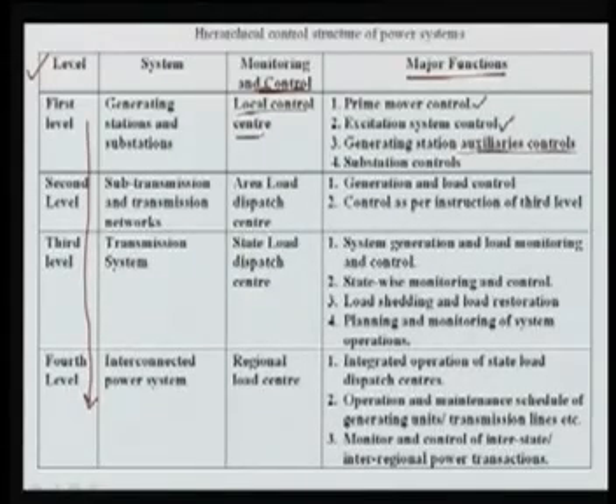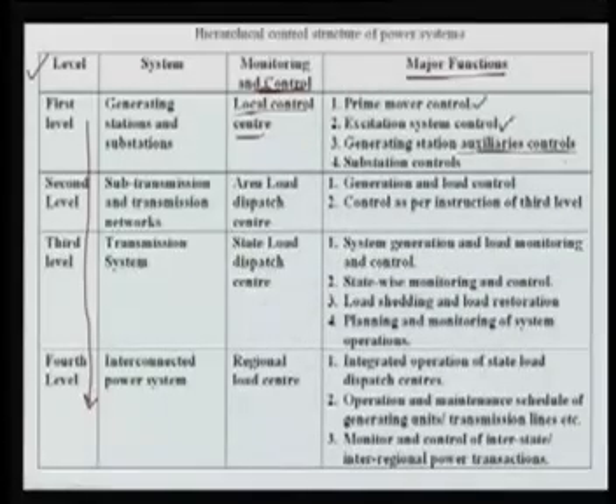You know, in any generating station we have a lot of auxiliaries. We have to have several auxiliaries for generating a single megawatt of power. For example, in the thermal power station we have the boiler feed pump, we have the condensate pumps, condensers, we have the PA primary air fan, we have the FD fans, we have ID fans, we have the coal mills, ball mills. So several units, several motors, and they are equipped with various controls, the individual control units. So here we require the various control functions, they are in that unit itself, and that must be performed, and that comes under the first level of control of the power system.